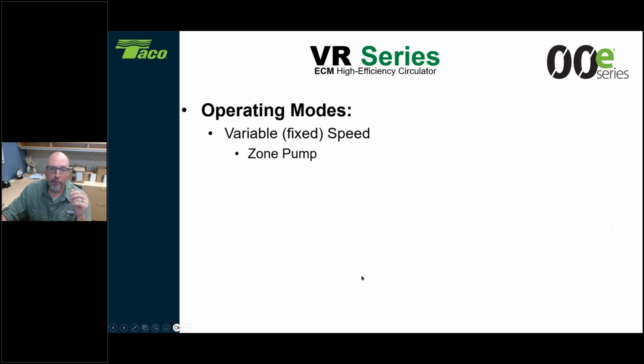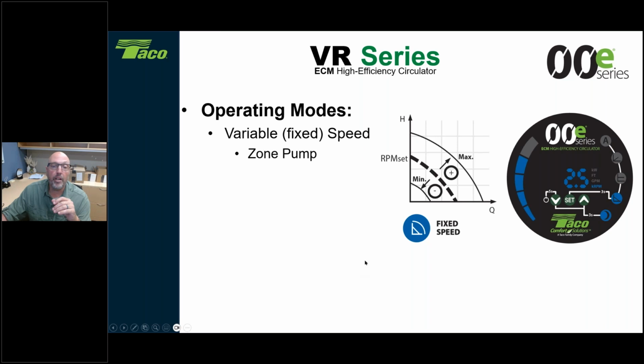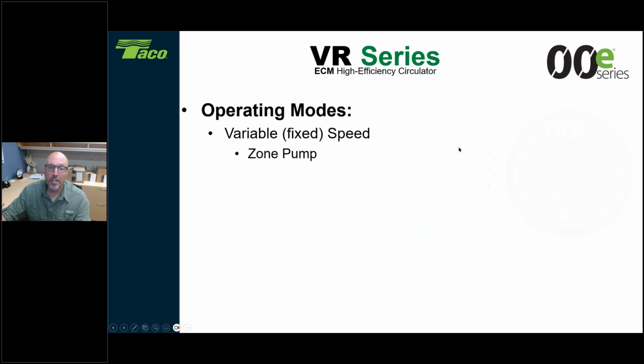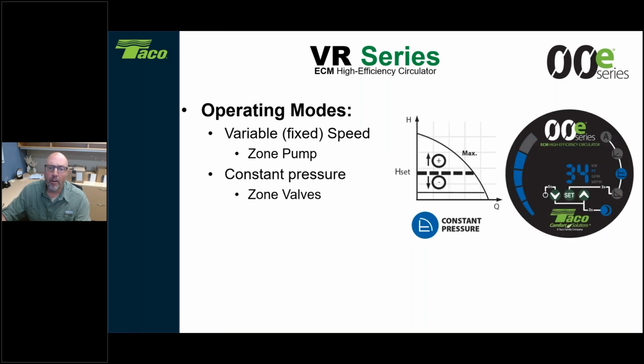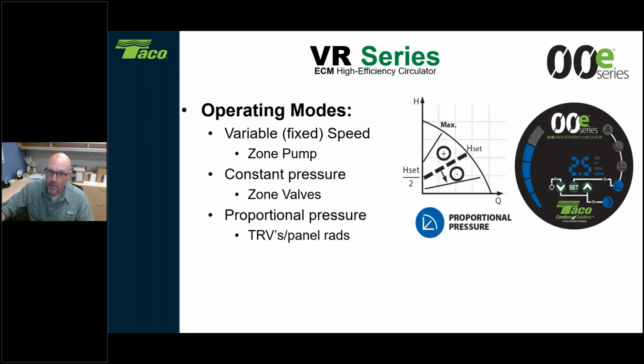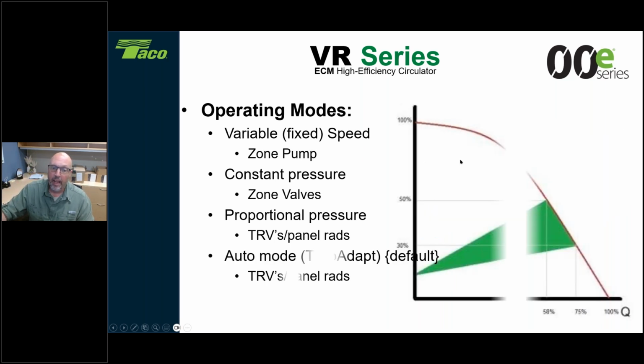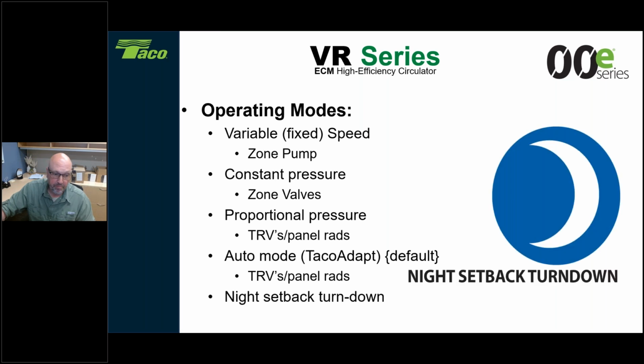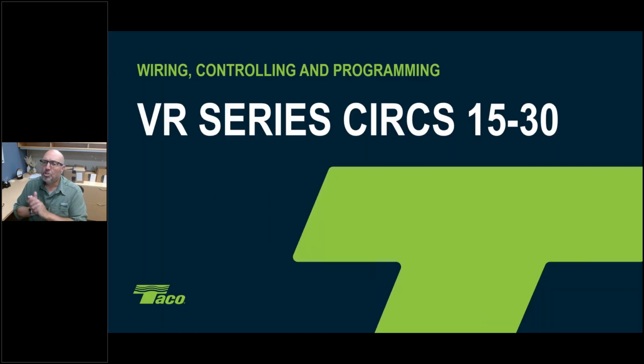All right, and like I said, here are those operating modes again that I talked about. I'm sorry, let me go back a slide. So here you can see the fixed speed mode. You're adjusting it based upon RPM of the circulator itself. Here's your constant pressure mode, where we're adjusting the maximum head that the circulator is going to operate on, and we'll change its speed as the flow changes, and maintain a constant discharge pressure. Here's our proportional pressure mode. This one here will slide up and down as your valves are slowly opening and closing. And then there is our auto mode, which happens to be the default mode of the circulator itself. And there's the night setback.